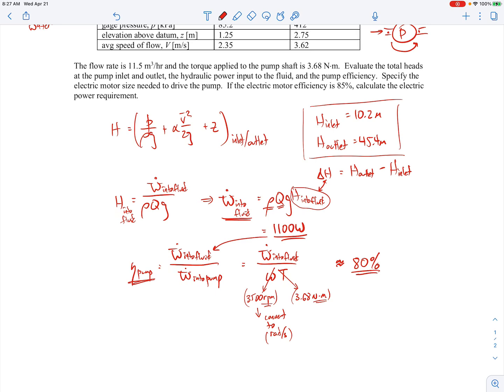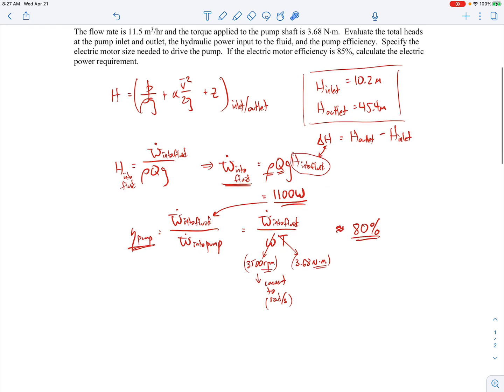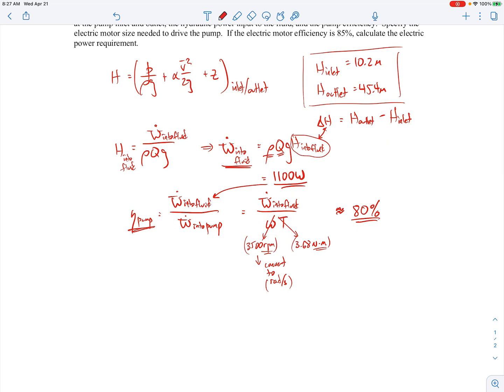The next thing we need to do is specify the electric motor size needed to drive the pump. Since the pump is only 80% efficient, we need to find the power that we have to put into the pump, which is omega times the torque. When you work out those numbers, that comes out to be about 1,350 watts. Our electric motor needs to provide at least that much power to drive the pump.